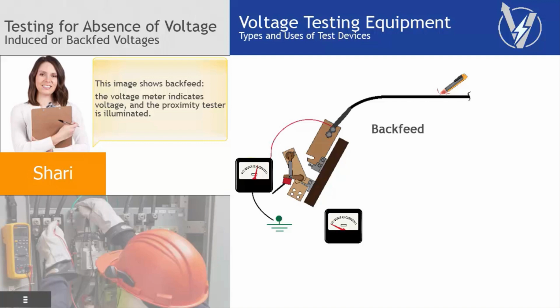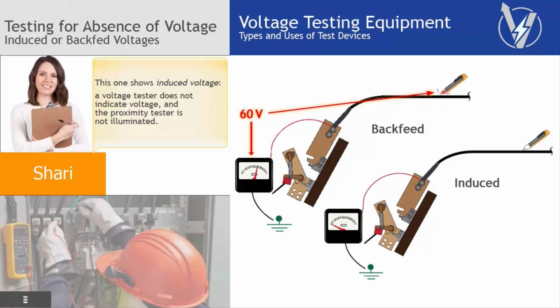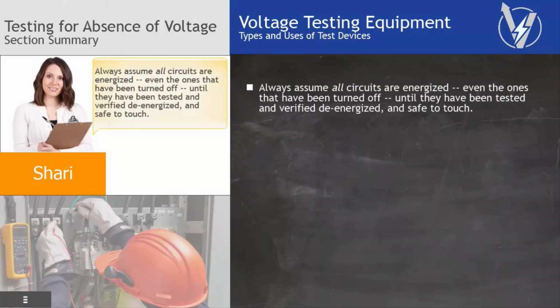This image shows backfeed. The voltage meter indicates voltage, and the proximity tester is illuminated. This image shows induced voltage. A voltage tester does not indicate voltage, and the proximity tester is not illuminated. Always assume all circuits are energized, even the ones that have been turned off, until they have been tested and verified de-energized and safe to touch.